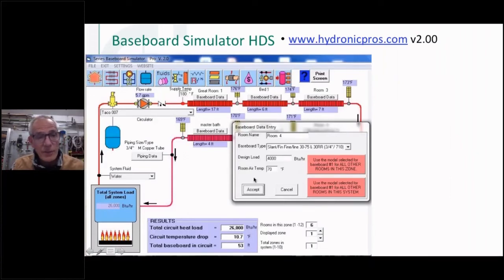So when you design a fin tube system, John Siegenthaler sells this little simulator software here. It's really nice. It's got a bunch of different toolbars across the top. So I can do a heat load, a baseboard fin tube. I can do a circuit simulator. I can size expansion tanks. I can correct for different percentages of glycol, insulation factor on pipes, how that changes the heat loss, some fuel cost comparison. This one's really handy too. It's a buffer tank sizer.